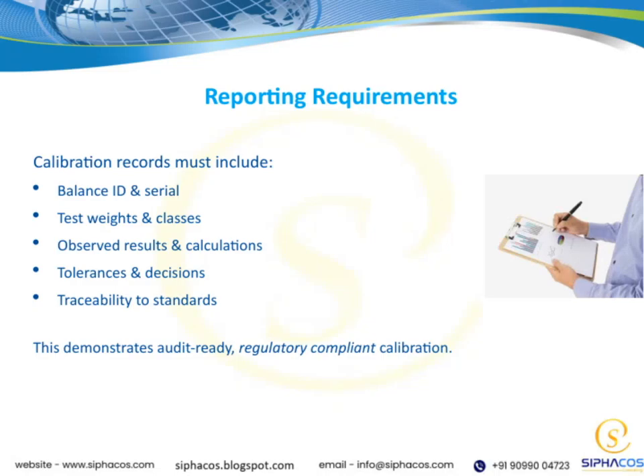Now, let's talk about the reporting requirements for calibration records. It's essential that these records include specific details to ensure accuracy and traceability. First, we need to record the balance ID and serial number so we can precisely identify which instrument was calibrated. Next, documenting the test weights used, along with their classes, helps verify the calibration process and ensures we're using appropriate standards. We also need to include the observed results and any calculations performed during calibration. This transparency allows us to review the process and confirm everything was done correctly.